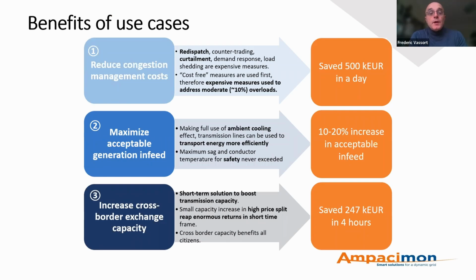So what does it deliver? Well, of course, it reduces congestion costs. It allows operators to avoid counter trading, to avoid curtailment, to avoid load shedding. You know, all these kinds of very expensive measures, by simply using the existing infrastructure closer to its true limits, but still in a completely safe way. And in this example, we'll come to it in a minute, the operator can save up to €500,000 a day. So needless to say, the payback on these investments is almost instantaneous.